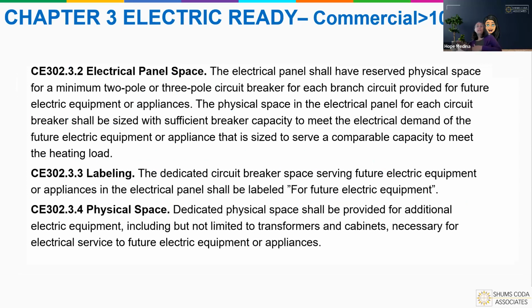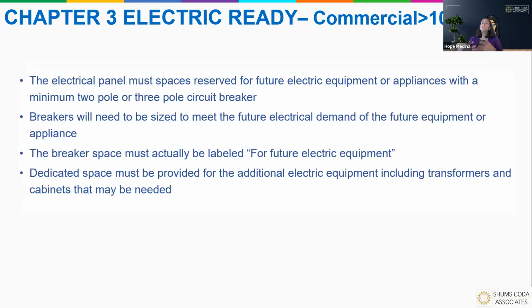Now when we talk about the electrical panel, it's very similar to what we saw with the 10,000 square feet rule. You still have to have a 2-pole or 3-pole circuit breaker reserved for that future equipment. It needs to be sized so that whatever future electric equipment is installed can meet the demand. You've got to have the space, it's got to be labeled, and again we have to have dedicated space provided for the additional equipment.